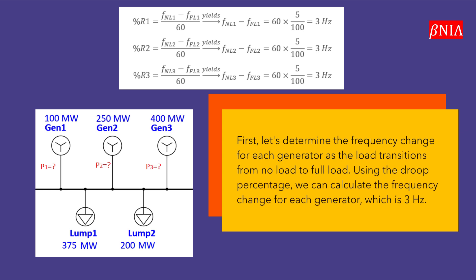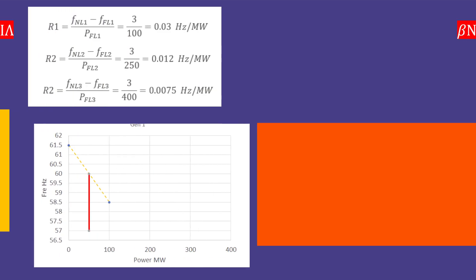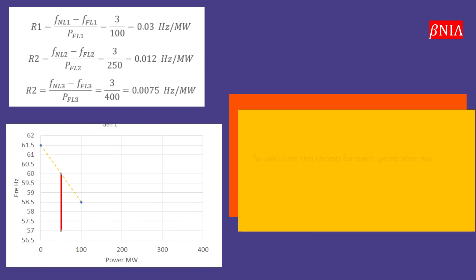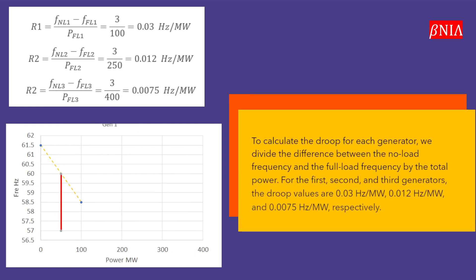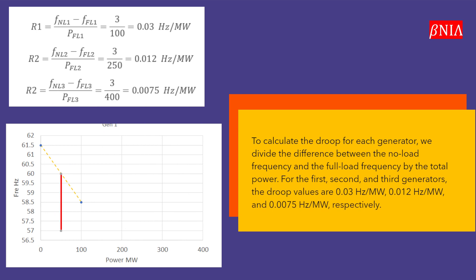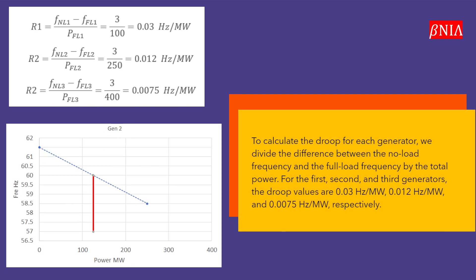Using the droop percentage, we can calculate the frequency change for each generator, which is 3 Hertz. To calculate the droop for each generator, we divide the difference between the no-load frequency and the full-load frequency by the total power. For the first, second, and third generators, the droop values are 0.03 Hertz per megawatt, 0.012 Hertz per megawatt, and 0.0075 Hertz per megawatt respectively.